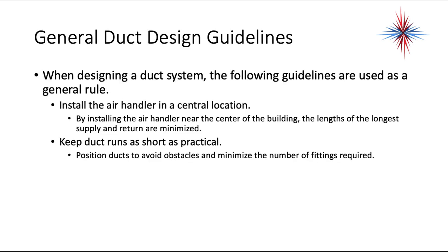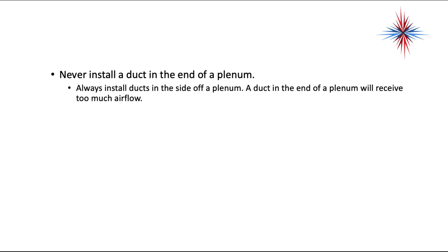When designing a duct system, the following guidelines are used as a general rule. Install the air handler in a central location — by placing it near the center of the building, the lengths of the longest supply and return runs are minimized. Keep duct runs as short as practical. Position ducts to avoid obstacles and minimize the number of fittings required. Never install a duct at the end of a plenum; always install ducts in the side of the plenum, as a duct at the end will receive too much airflow and will be noisy.